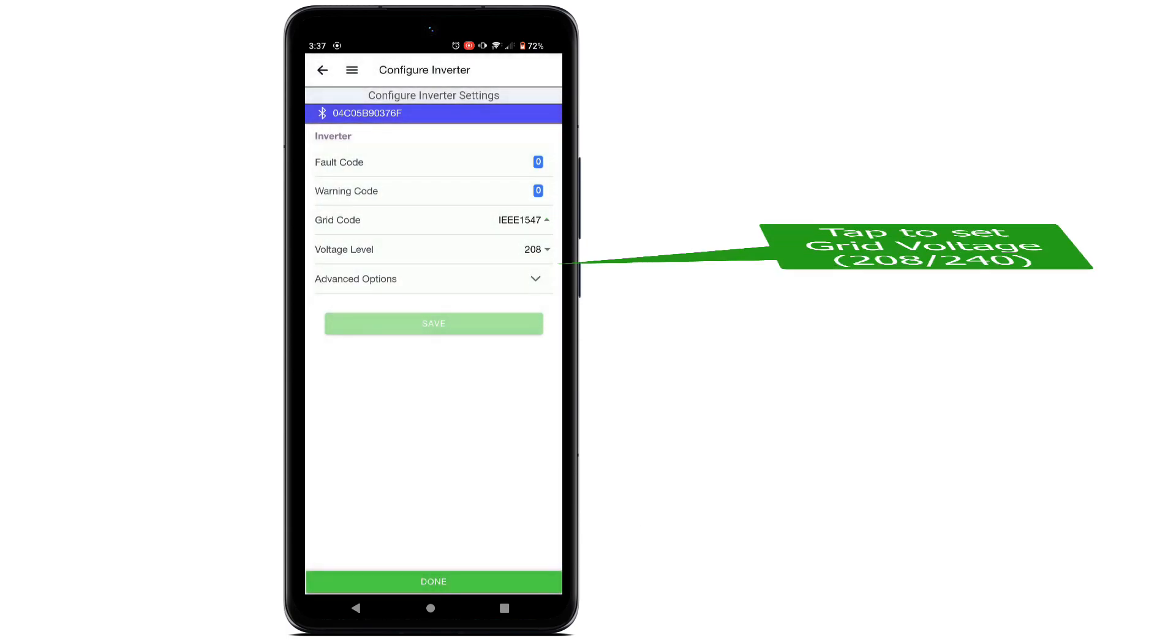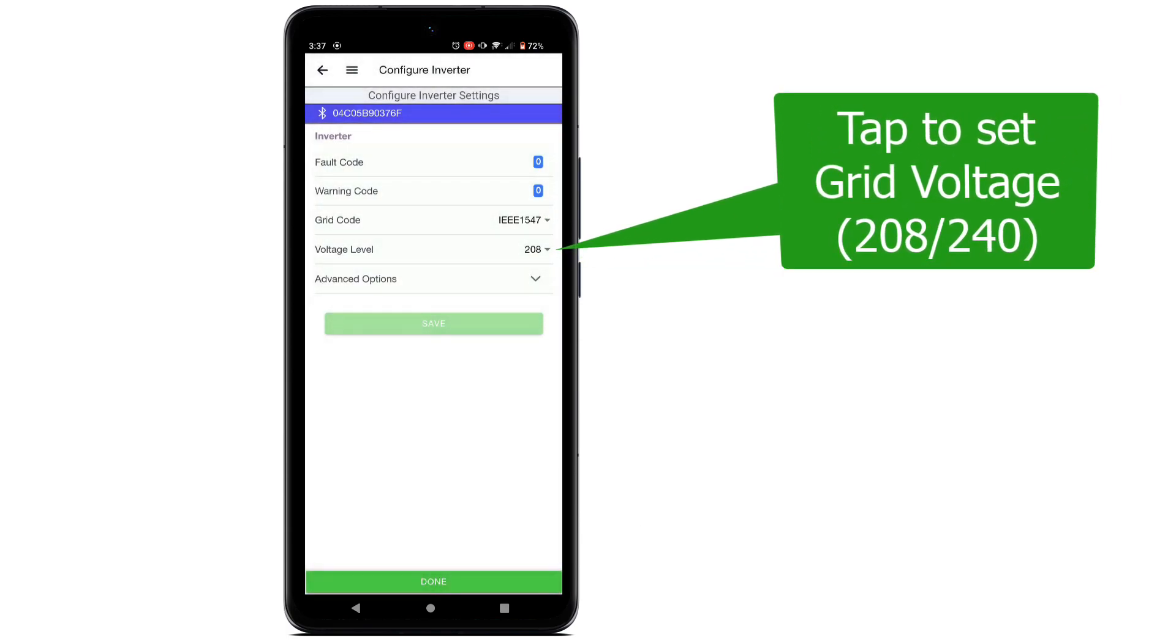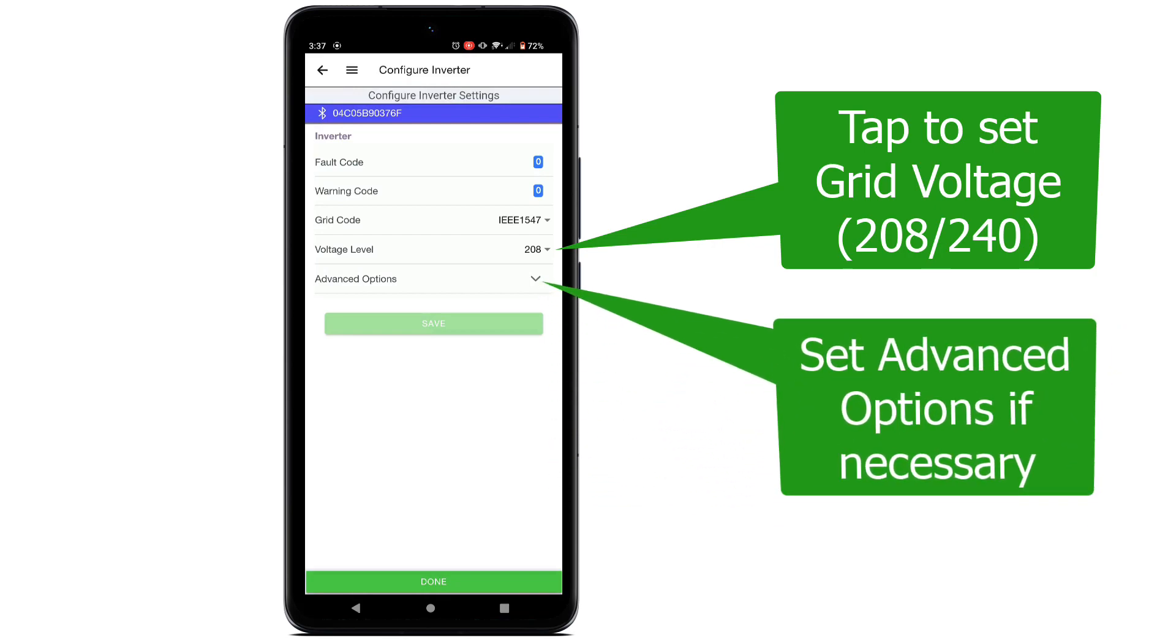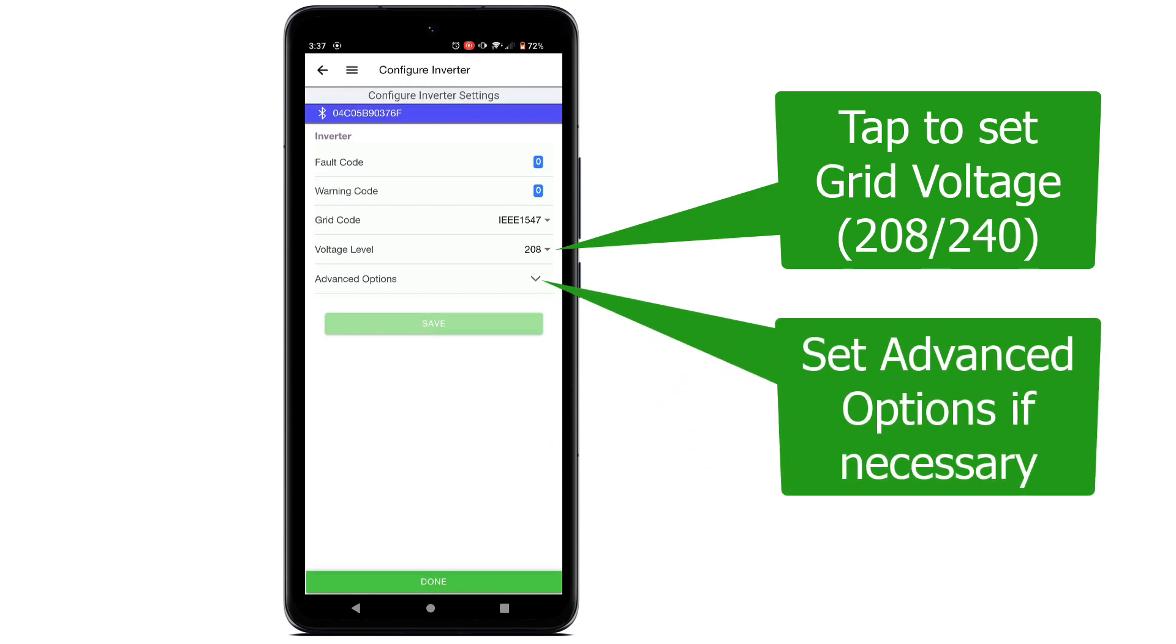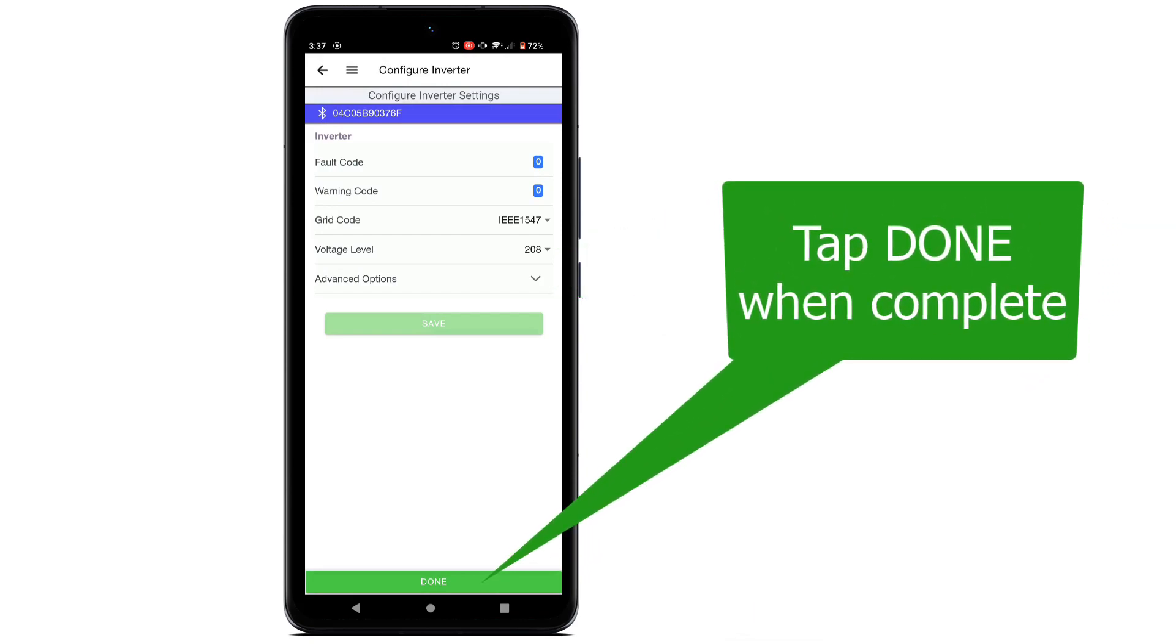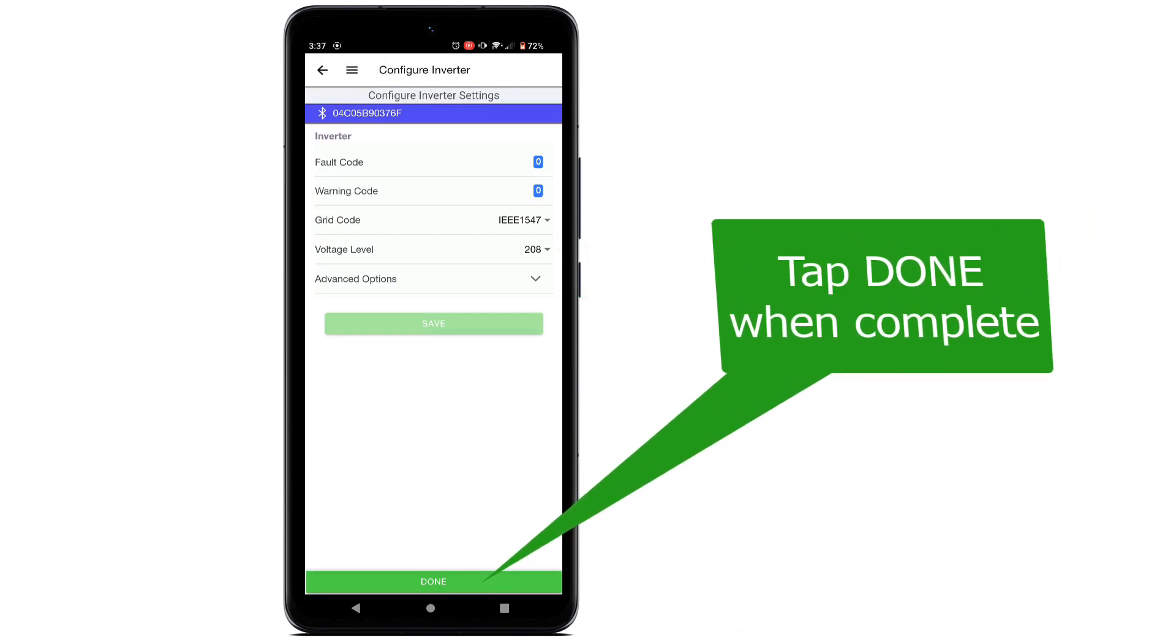Select the grid code from the drop-down menu appropriate for your utility. Enter the site grid voltage, either 208 or 240. Enter the advanced options if necessary. Most of the time these will be optional. Tap Done to return to the EI setup screen.